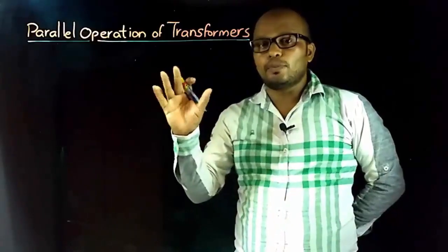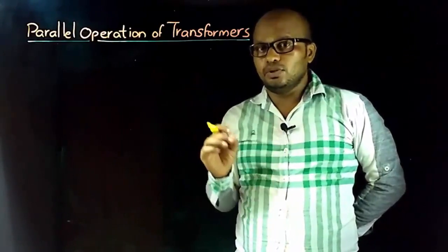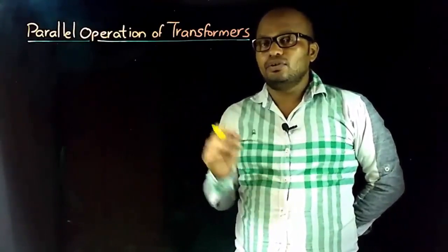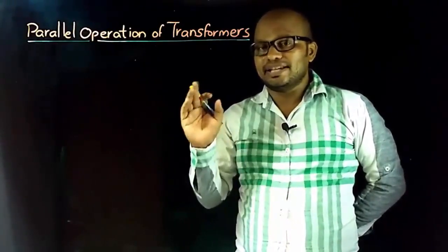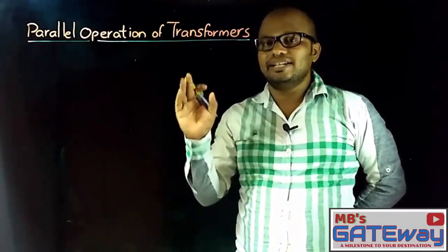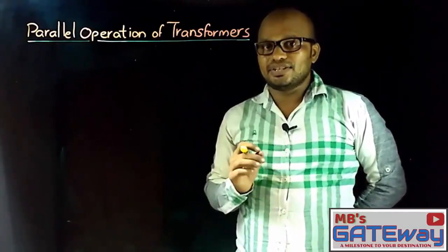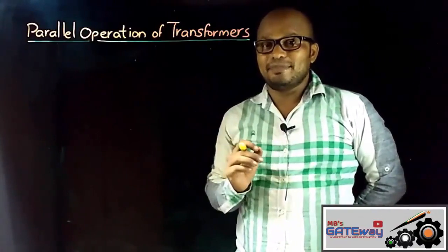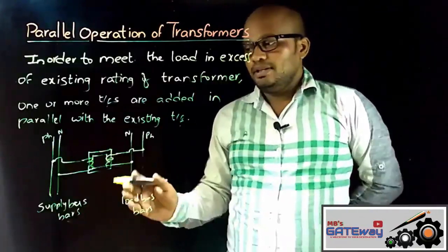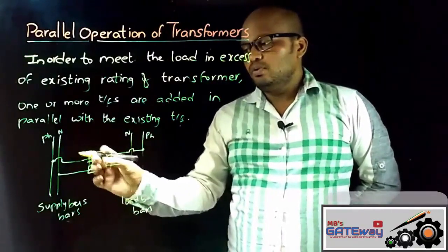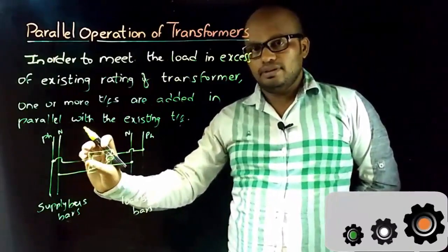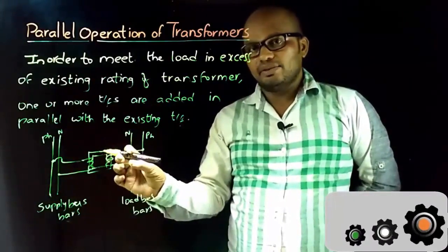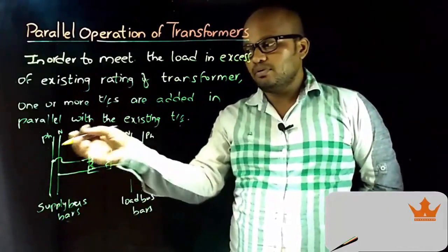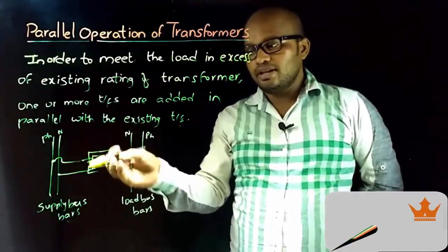Now, parallel operation of transformers. In order to meet the load in excess of the rating of the existing transformer, a transformer or more transformers are added in parallel with the existing transformer, which is called parallel operation of transformers. This is the existing transformer whose primary windings are connected across the supply bus bars and secondary windings are connected across the load bus bars, and here the transformer is taking power from the supply bus bars and delivering that power to the load through load bus bars.